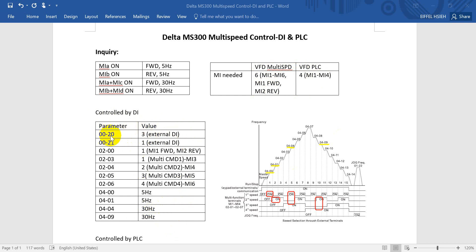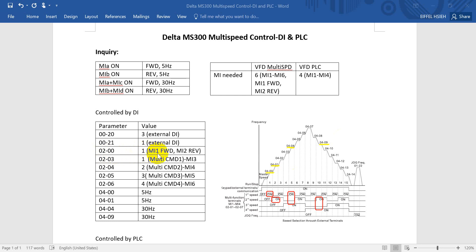For the main frequency we use 3, which means external terminal, and this one is run/stop control by also external terminal. Then for 02.00 this one is for the wiring method. For the default setting, MI1 means forward, MI2 means reverse, and then we will define MI3 as multi-speed command 1, etc.